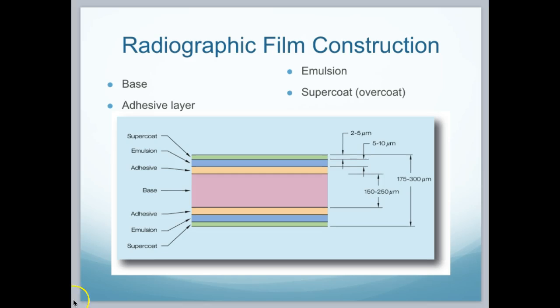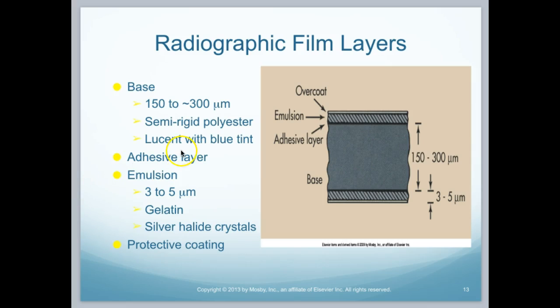Let's go over the components of a radiographic film, polyester radiographic film. Starting with the base layer, right in the center, it's connected to an adhesive layer that keeps the emulsion intact, and then we have a supercoat to help the durability. The base layer is 150 to 300 micrometers. It's made of semi-rigid polyester and is tinted with a blue tint. This blue tint helps to reduce the fatigue on the radiologist's eyes.